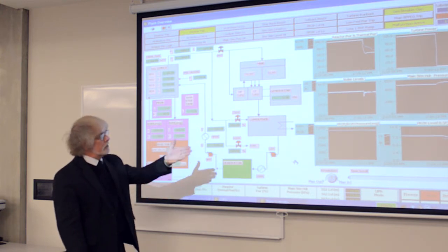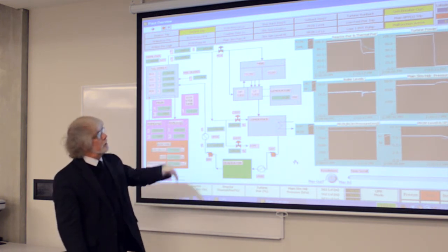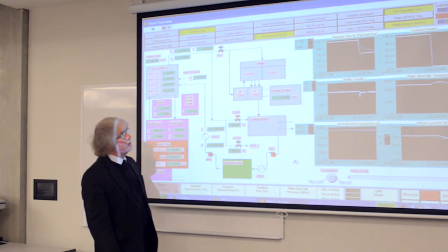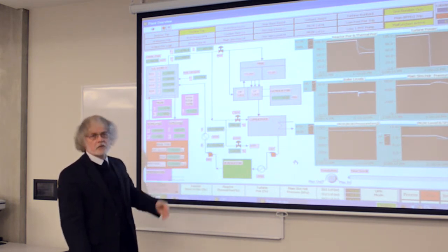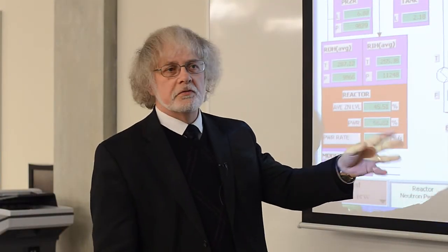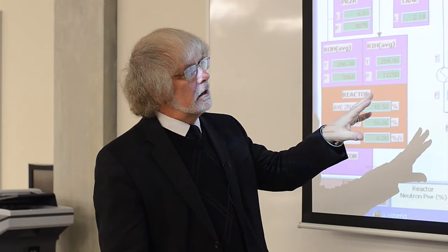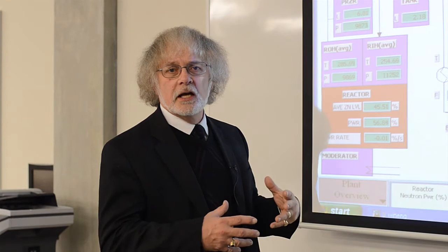You can see here our pressurizer level and set point changing, boiler levels responding. You can see the reactor power has decreased. We just got an alarm of steam generator high level, and you can see our turbine output went from 100% down to 0. At any point, the student can move from run mode to freeze mode, and that will lock the transient so that we can focus on a part of the scenario to understand it in depth.